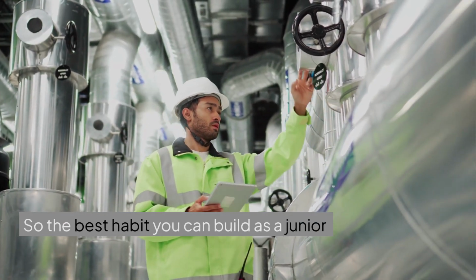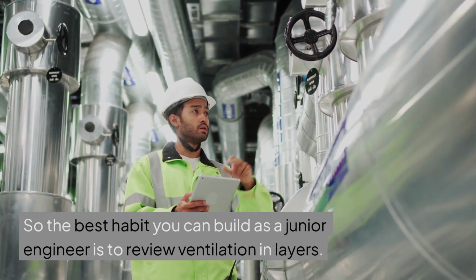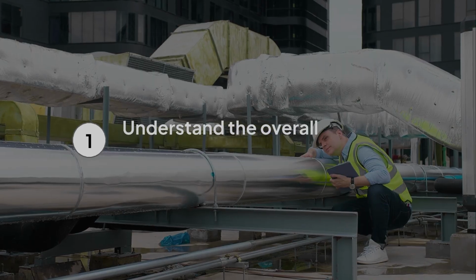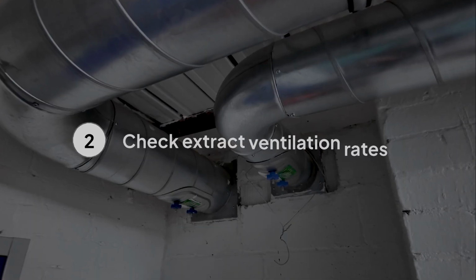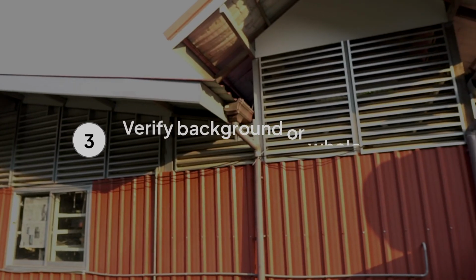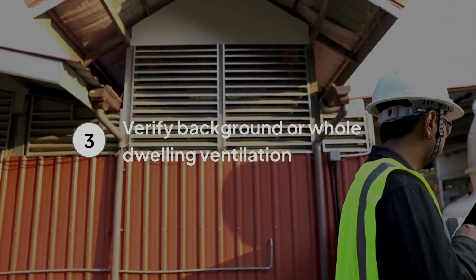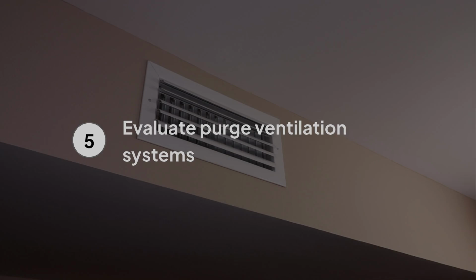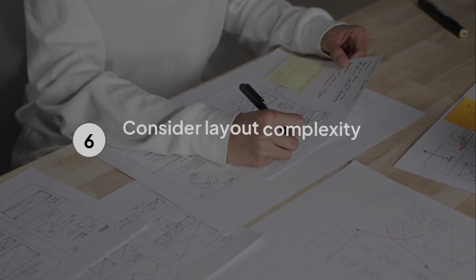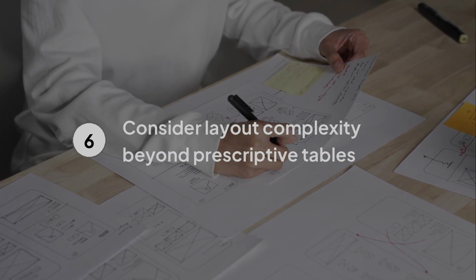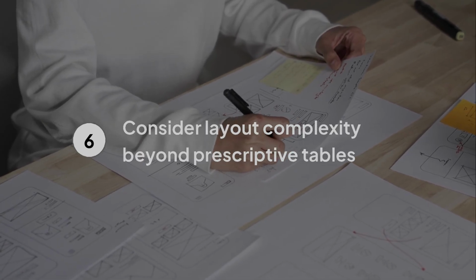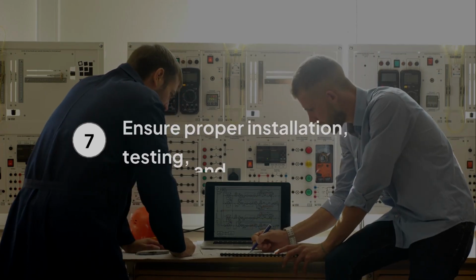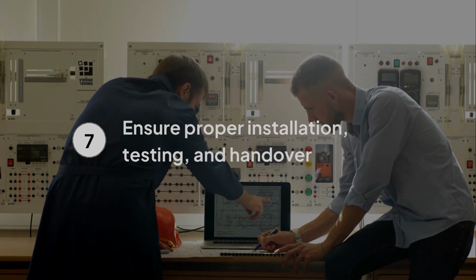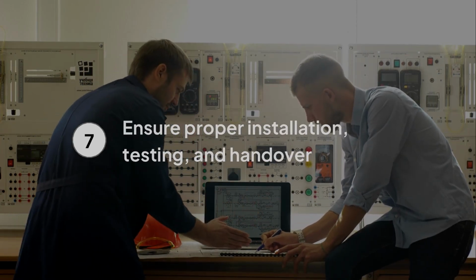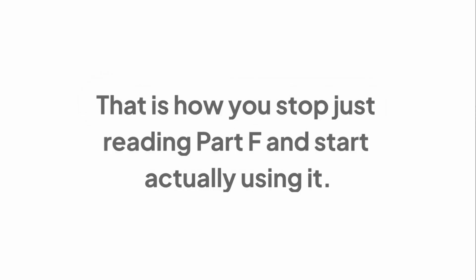So the best habit you can build as a junior engineer is to review ventilation in layers. First, ask what the overall strategy is. Then check the extract rates. Then check the background or whole dwelling ventilation route. Then check the transfer path. Then check purge. Then check whether the design is relying on a simple prescriptive route in a layout that may need more detailed thinking. And finally, remember that the system still needs to be installed, tested, commissioned, and handed over properly. That is how you stop just reading Part F and start actually using it.